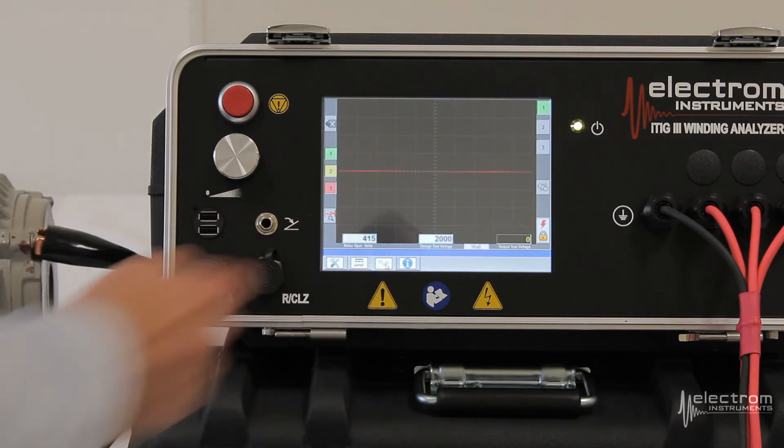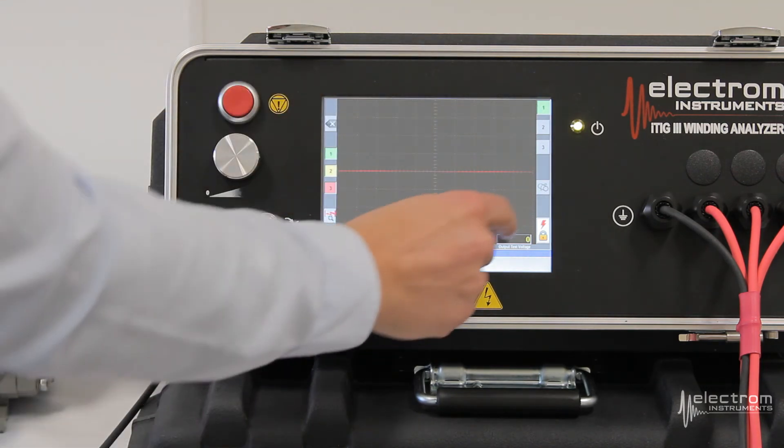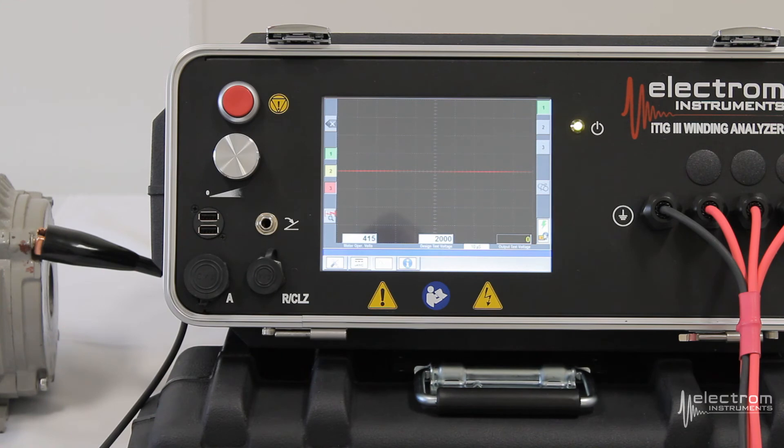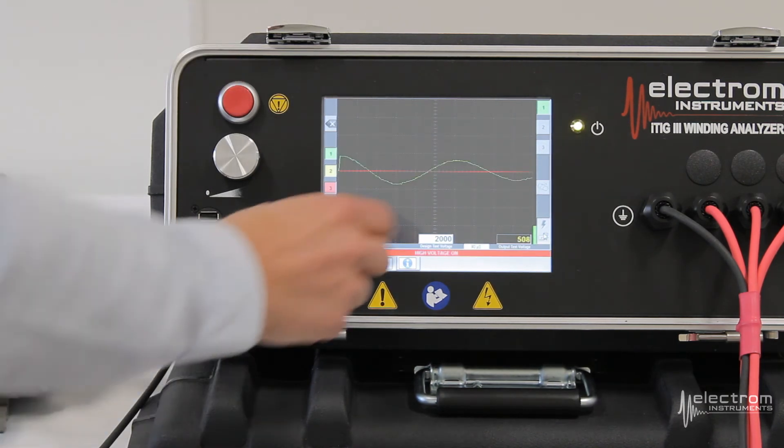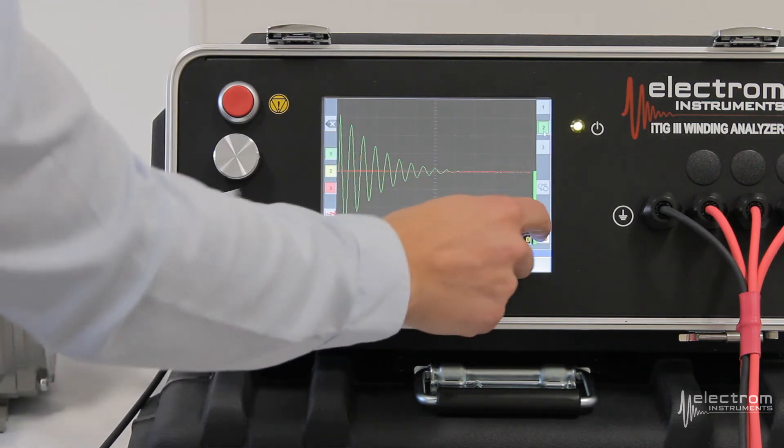Last step here is the surge test. Lead 1 will be the first one to be energized. You arm the instrument. Press the red button. It will automatically set the time base and voltage scale. Drive the voltage up to our design test voltage, 2000 volts in this case. Then you'll do the same for phase 2.